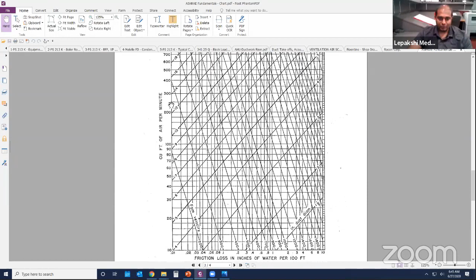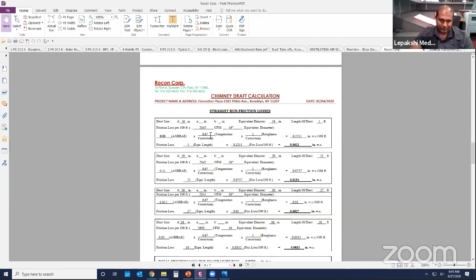So now you have 2800 CFM. On this page, you have only up to 2000, but we have 28 something, right? Or 24 something. So now you go over here for that particular sized duct, and with the CFM over here, you'll come up with the friction loss for every 100 feet of that one. So I come up with 0.33 in my calc. That's how you have to come up with this number. Once you have that, you have some correction factors for the temperature. I'm not going to go into detail on that. That's how you're going to calculate the friction losses for the straight run pipes.